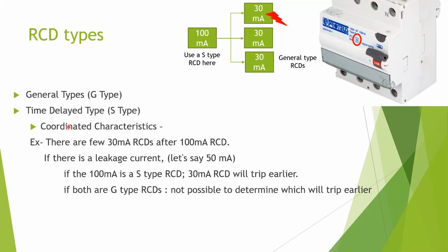But when it comes to larger buildings, let's say you have several floors with 30 milliampere RCDs, for the main distribution panel you can't put another 30 milliampere RCD, because there will be false trippings. If you only need to isolate one part of the building, and this one is 100 milliampere, if it is a general type, every RCD will trip instantaneously, cutting all the power supply to your building. So therefore we need to have delayed type RCDs. The two main types: the first is the general type, which operates instantaneously, and the second is the time delayed type. So 100 milliampere, here it is an S type.